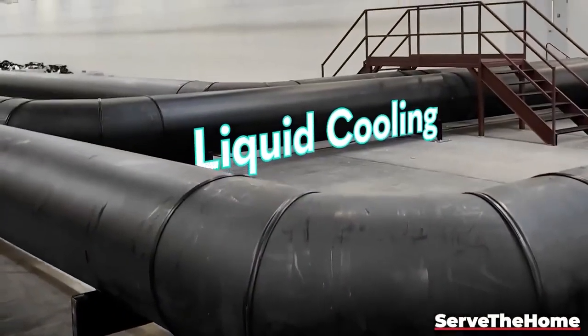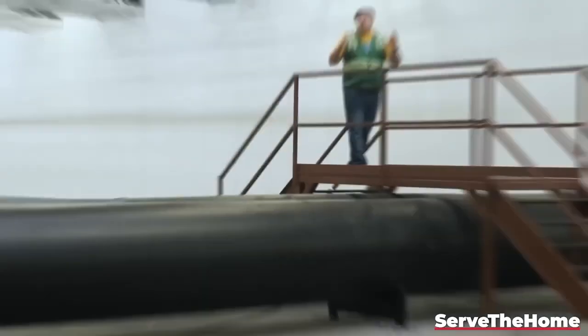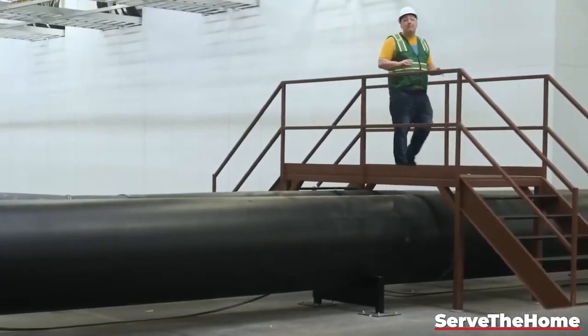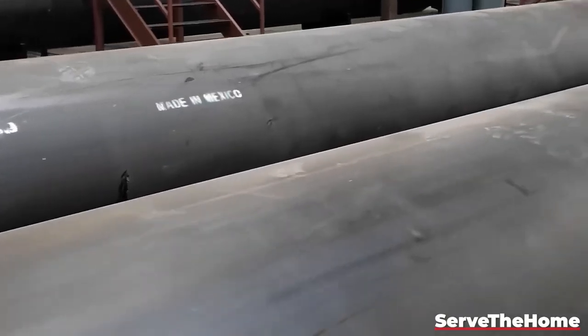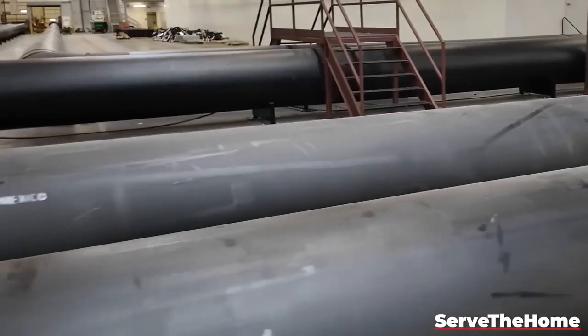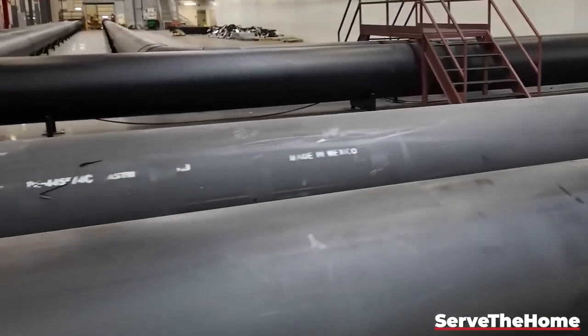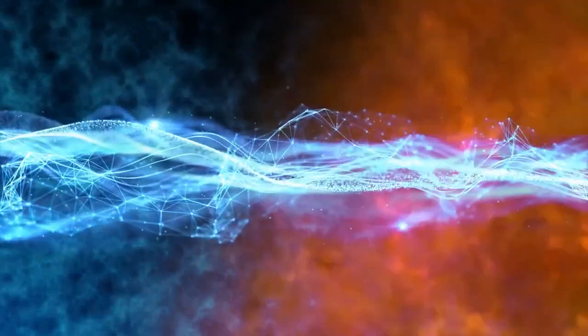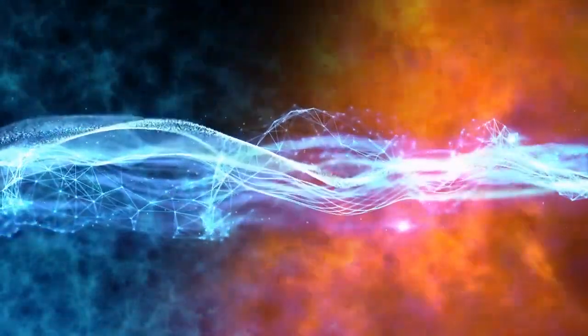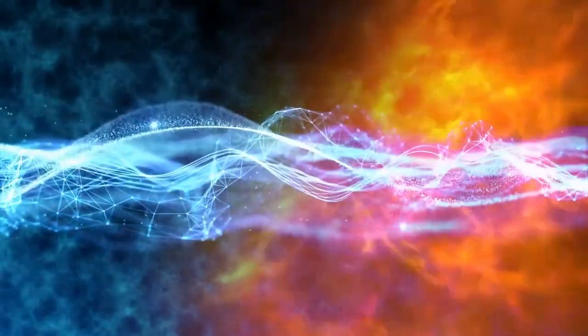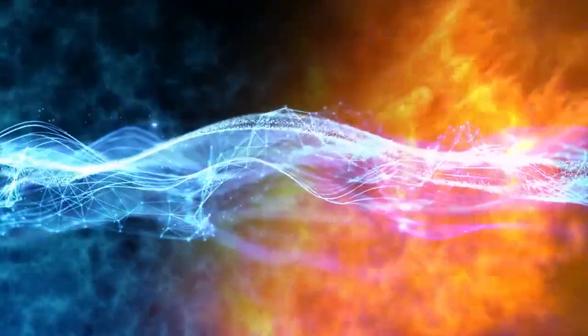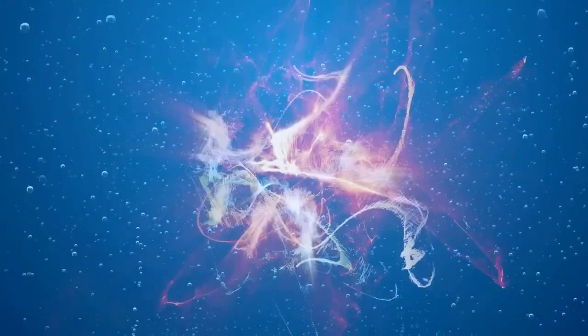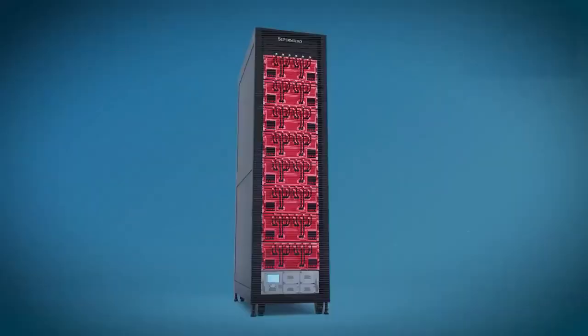Below the GPU cluster is a network of giant pipes that move vast amounts of water in and out of the facility. Hot water from the server is sent outside to a chiller, which lowers the temperature of the water by a few degrees before pumping it back in. This doesn't necessarily need to be cold water, though. Without getting too deep into thermodynamics, just remember that energy always travels from hot to cold. So as long as the temperature of the water is lower than the hardworking GPUs, which get pretty hot, then the excess heat energy will be drawn into the water as it flows past.